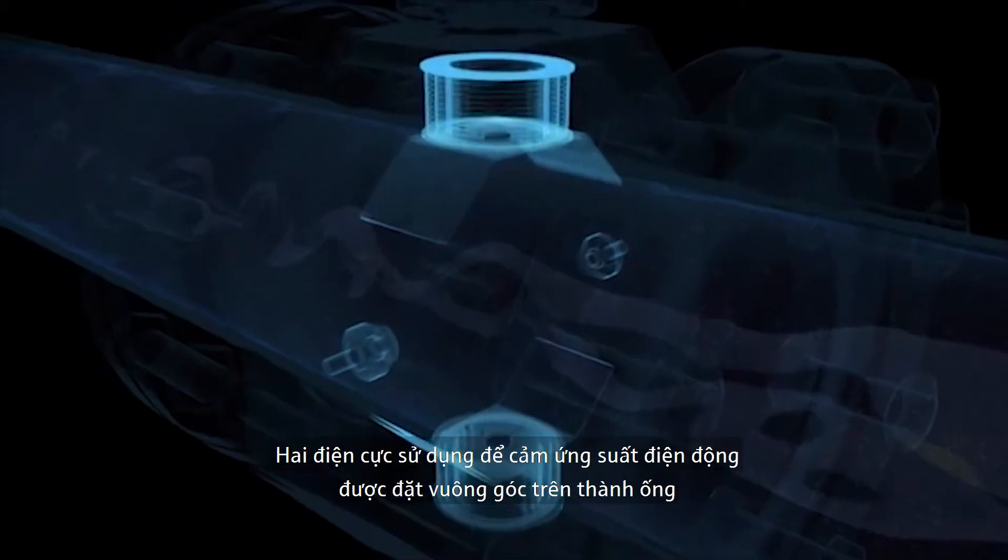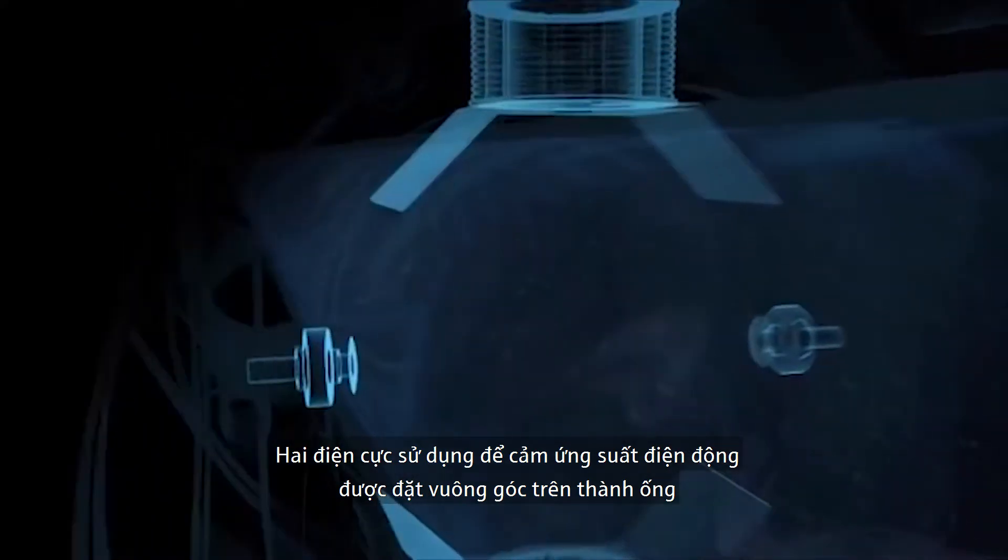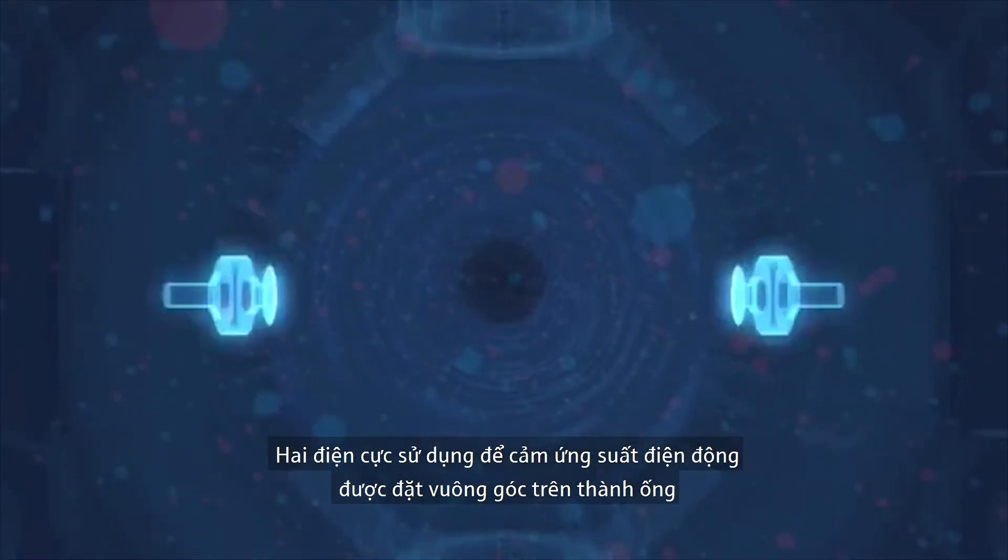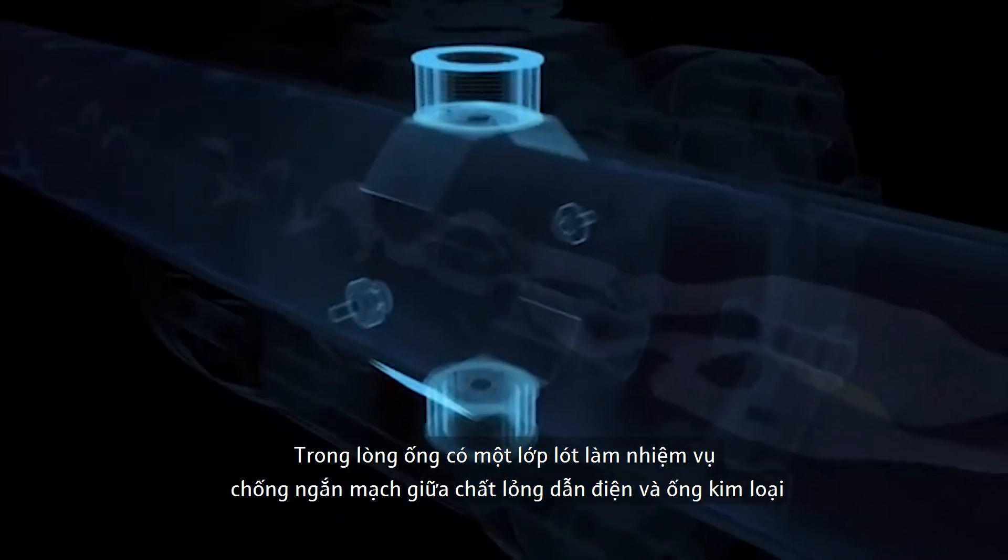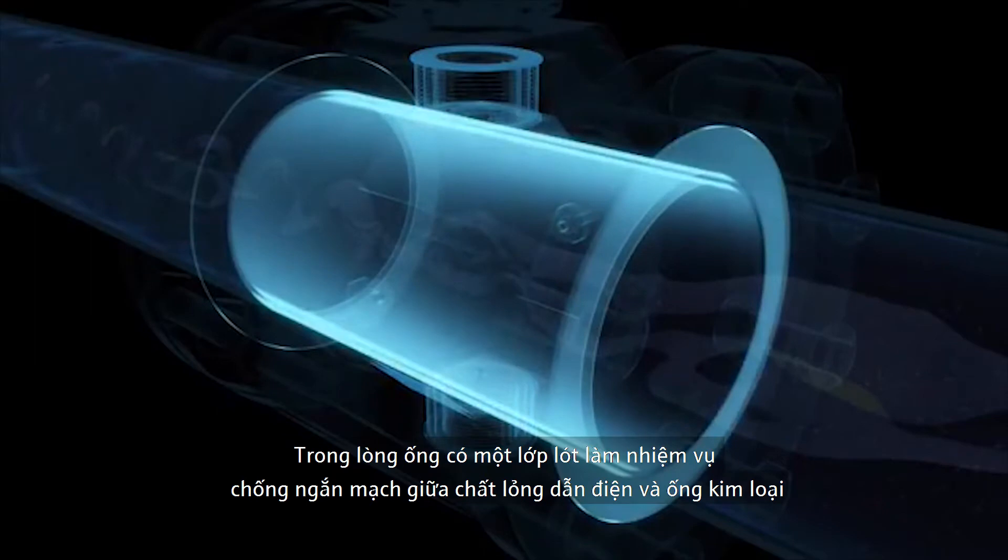Two electrodes which can pick up electrical voltages are installed at a right angle in the wall of the tube. The lining fitted on the inside wall prevents electrical short circuits between the conductive liquid and the metallic tube.